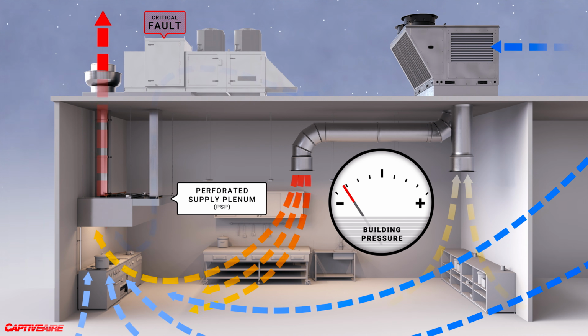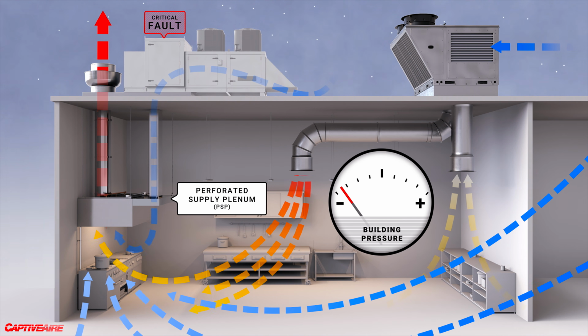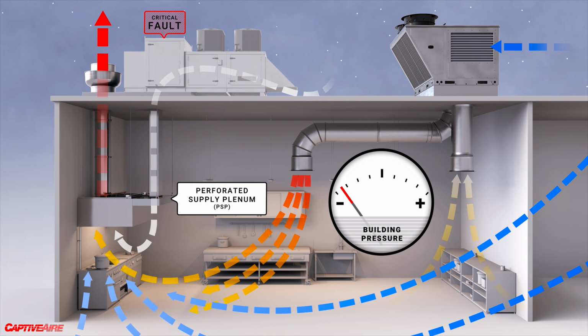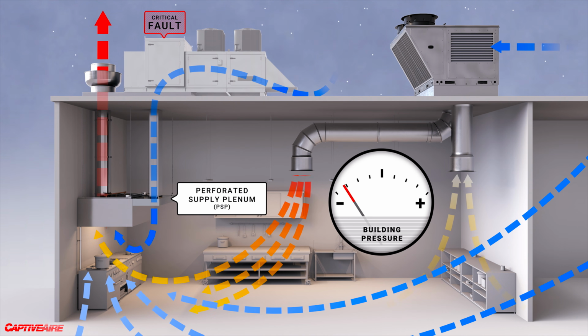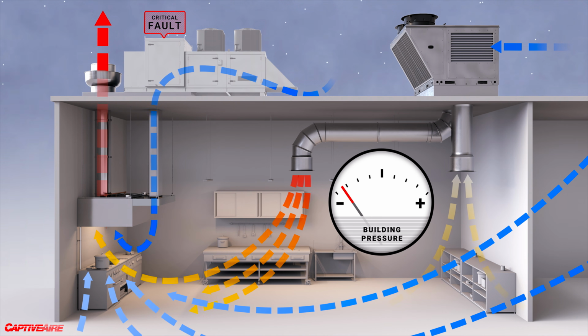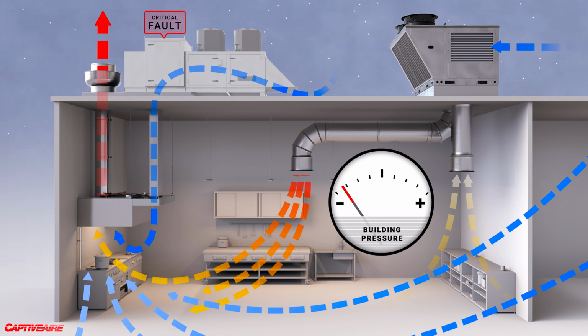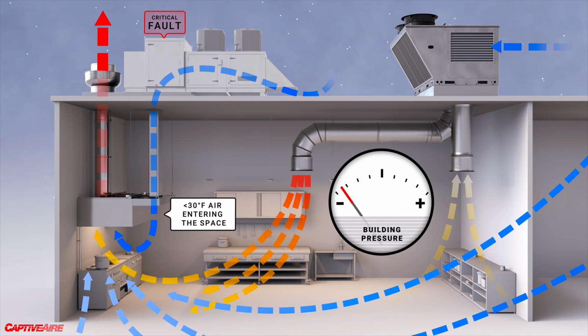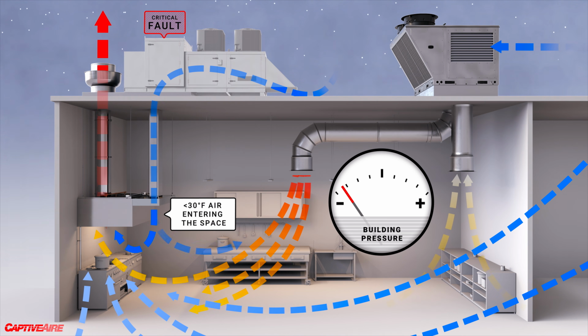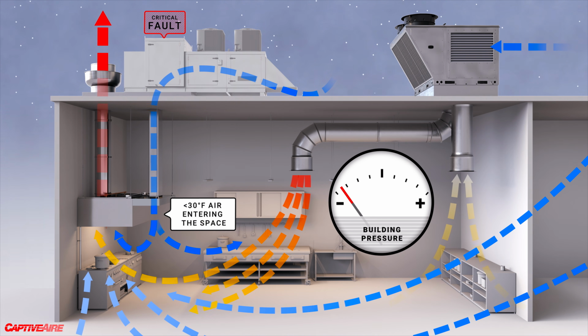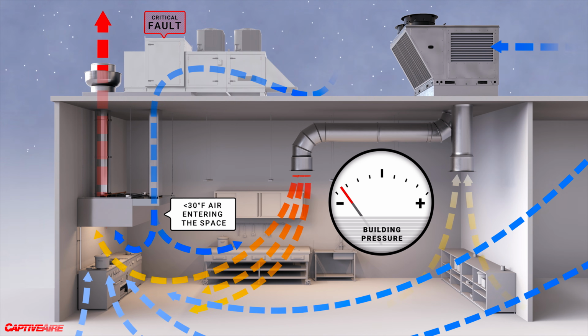And since that was going so negative in the space, that makeup air unit was now acting like a chimney, sucking air back into that hood. The temperature now was reading down to 27 degrees because that space was negative, and it's essentially dumping below 30-degree air directly into that kitchen, as well as everywhere else in that building that it's pulling in negative 20 when the doors open.